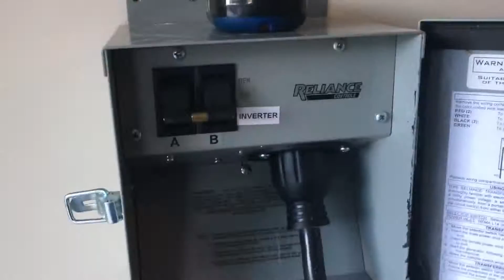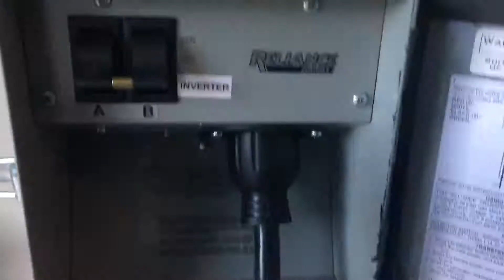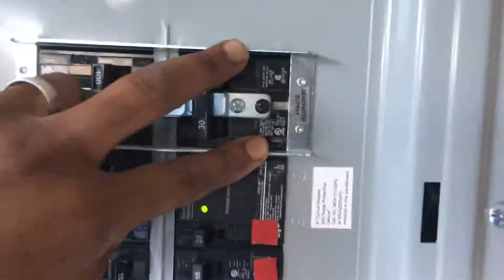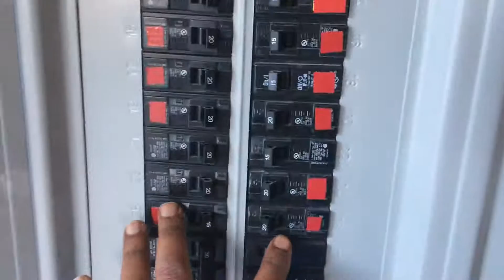I have a standard starter battery, and so far it's good to go. I've got it connected to my manual transfer switch here, going from inverter to generator. Flip it down for inverter, flip it up for the generator. This transfer switch feeds into this circuit breaker, and the power will either come from my solar or my generator, energizing these two branches of my circuits.